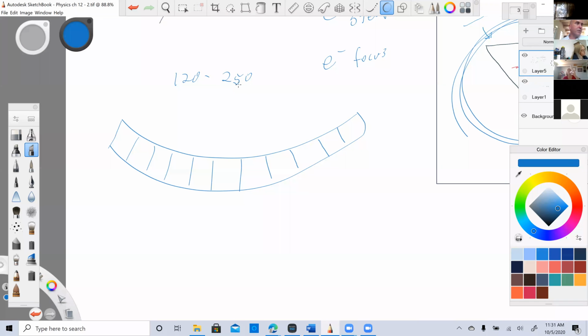Rectangular shaped strips of piezoelectric material side by side in a bowed line. So that's our curved. Also called convex, curvilinear array transducers. They are array because it's a group of them. The array is large. The acoustic footprint may be as long as 10 centimeters. The acoustic footprint is not the aperture.